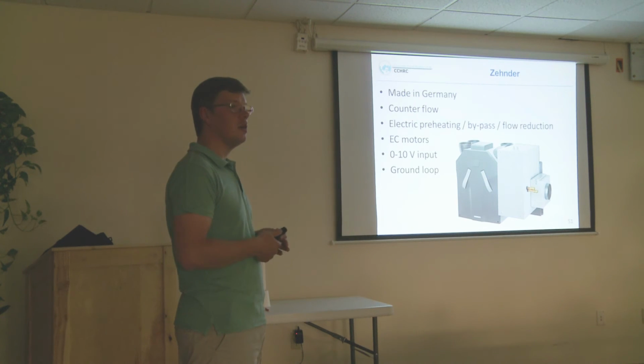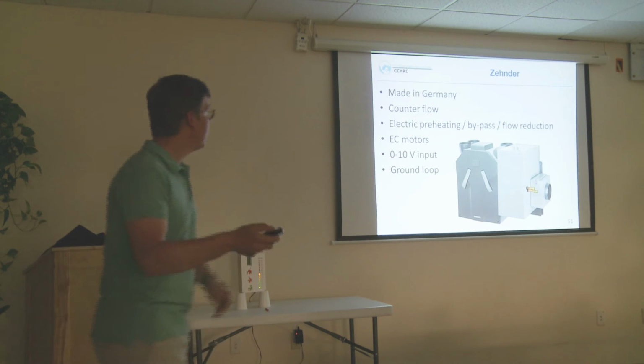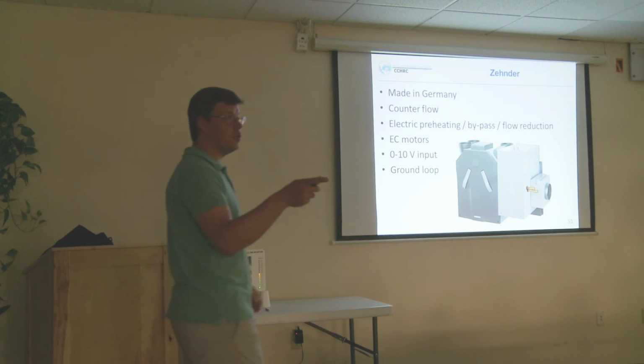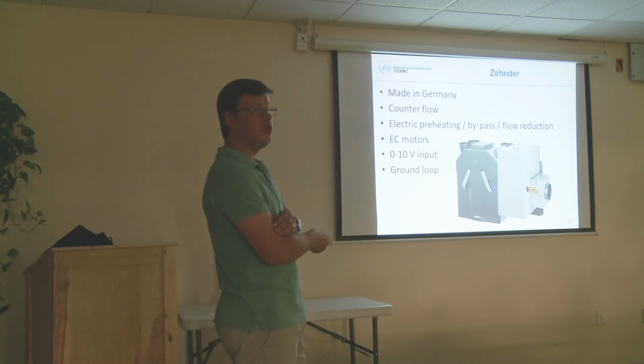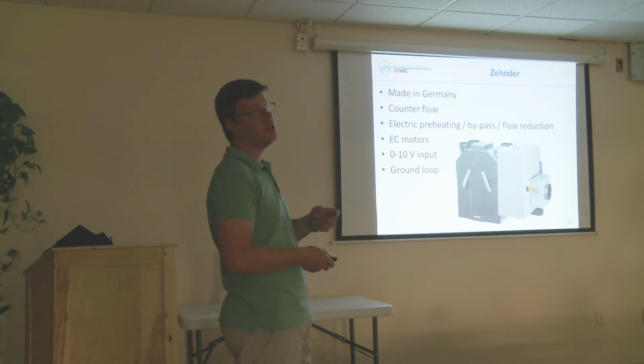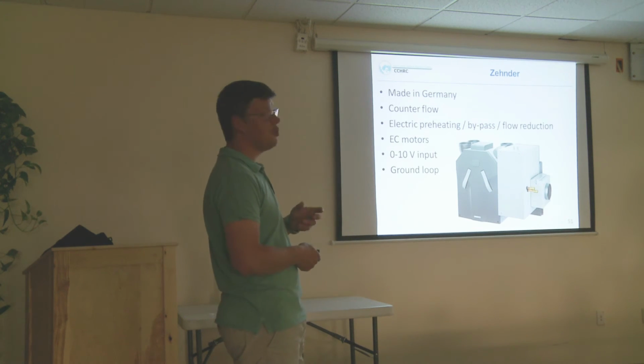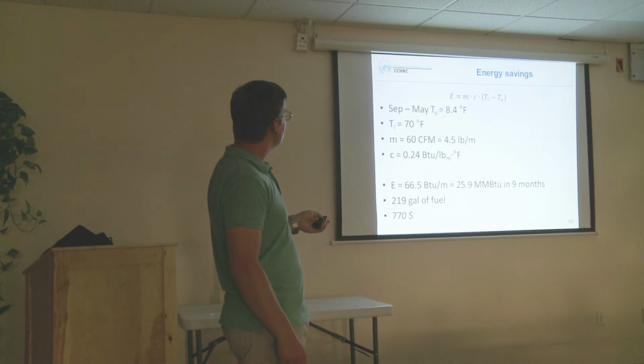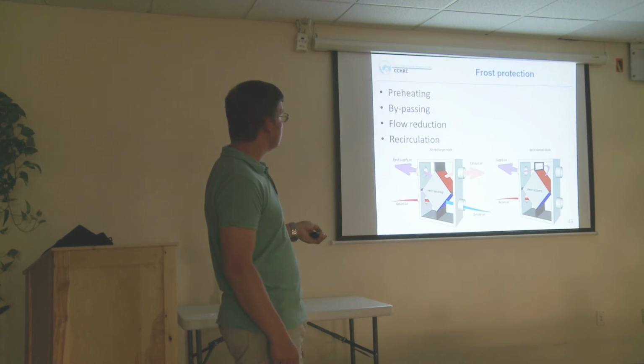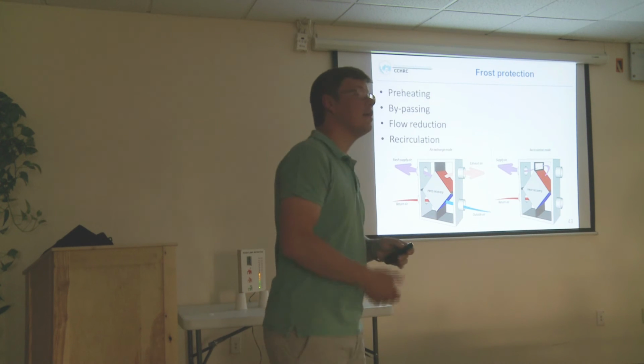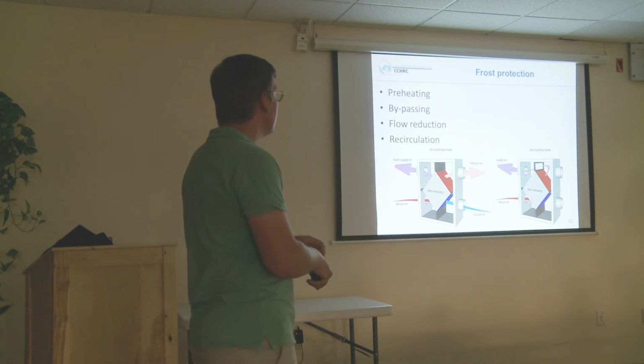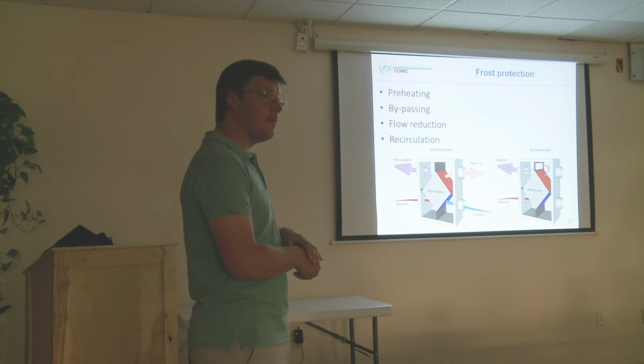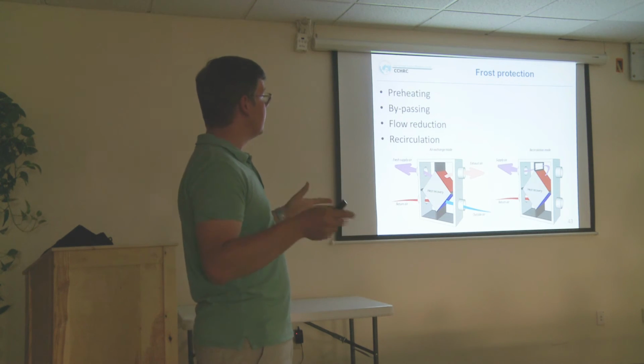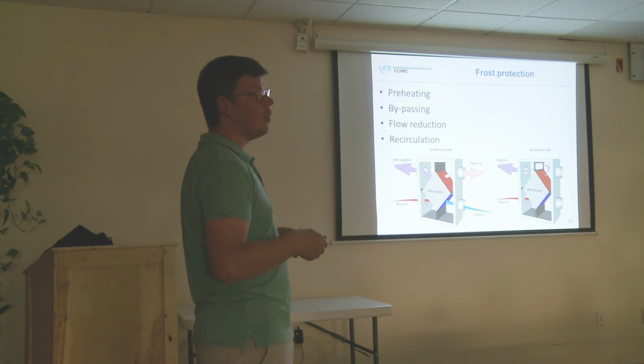If you don't make up for that, then you're going to reduce the indoor air quality by using the bypass. No, I'm sorry, the flow reduction would do that. For flow reduction, you have to make up for the air. If you have a bypass, it's all right because you have the same amount of fresh air coming in. It just doesn't get preheated in the heat recovery. Do you mean bypass or recirculation? Well, you mean this one? Let me see. Right, this one, the recirculation. That's a recirculation. And so that's a bad idea. That's the one that made the air quality worse. Yeah, that's right. It's a bad idea if you don't make up for that fresh air.